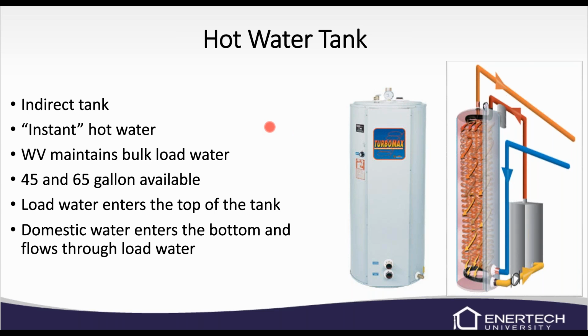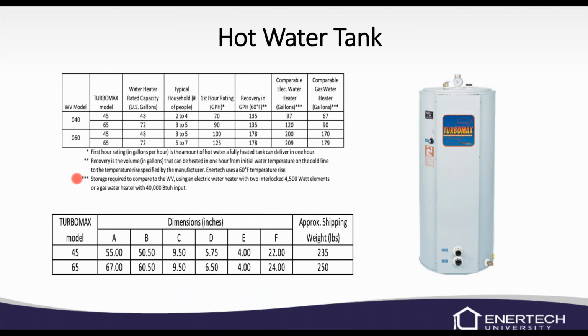Again, it's a 45 and a 65 gallon tank. And again, loaded in the top, out the bottom, domestic hot water in the bottom, out the top. Again, just remember that this comparison is in the IOM, so we can get the right size tank for you. If you got any questions on that when you're sizing it, just give us a shout.